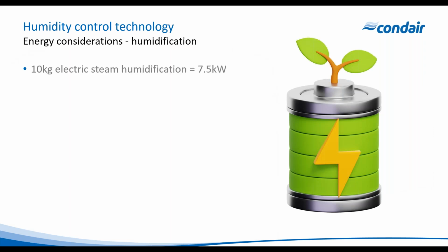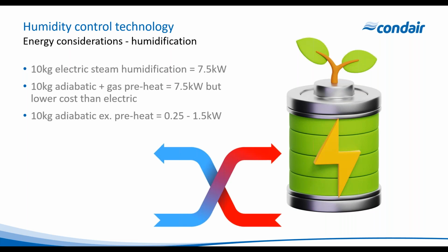Energy considerations for humidification. A pretty good rule of thumb is that for every 10 kilograms of steam that you're producing electrically, it's going to cost you 7.5 kilowatts of electrical energy. If we're doing that same 10 kilograms with an adiabatic system and gas preheating, it's still the same 7.5 kilowatts, but the cost of the gas preheating is lower because typically gas is a third of the cost of electricity. If we're using a 10 kilo an hour adiabatic unit and we're preheating with waste heat, so if you exclude the preheating, they're really cheap to run, 0.25 to 1.5 kilowatts. And it doesn't matter how big the unit is, you could be evaporating 1,000 litres of water and still have the same run cost for the humidifier itself. So these are all considerations that should be made when selecting.